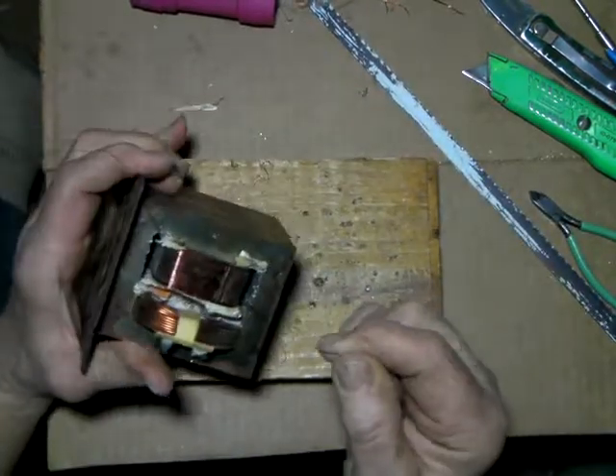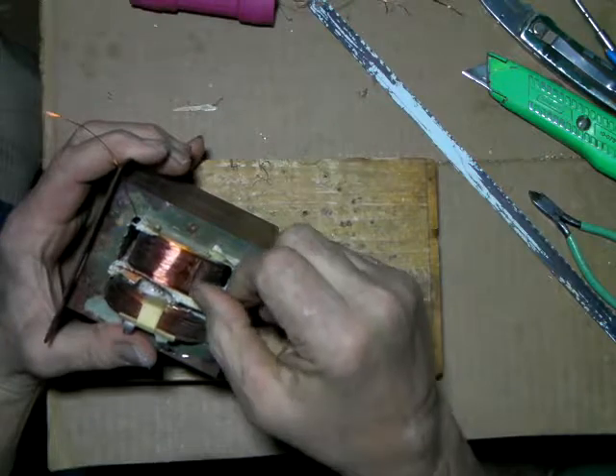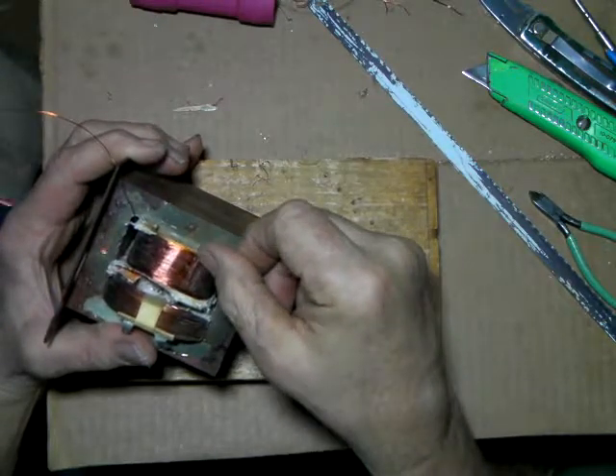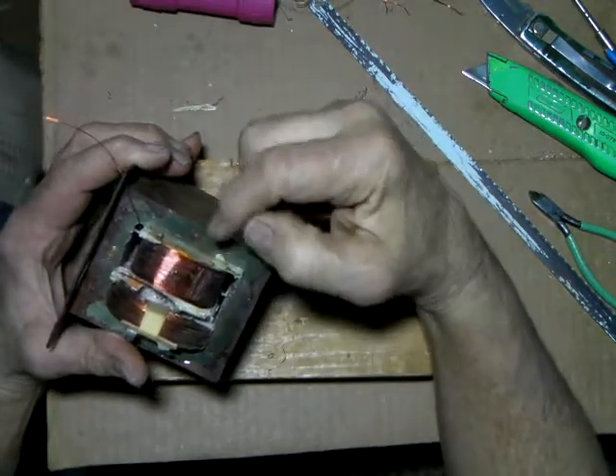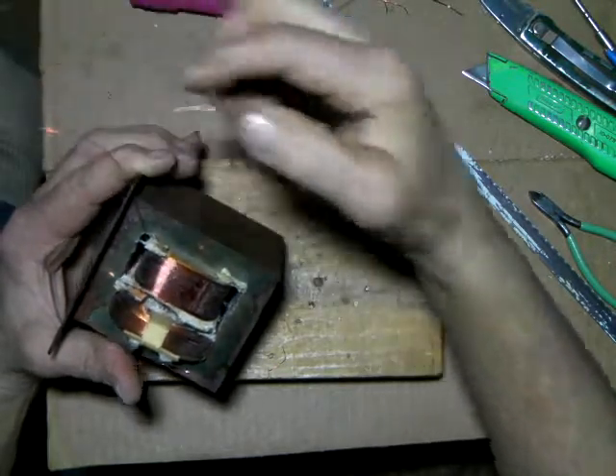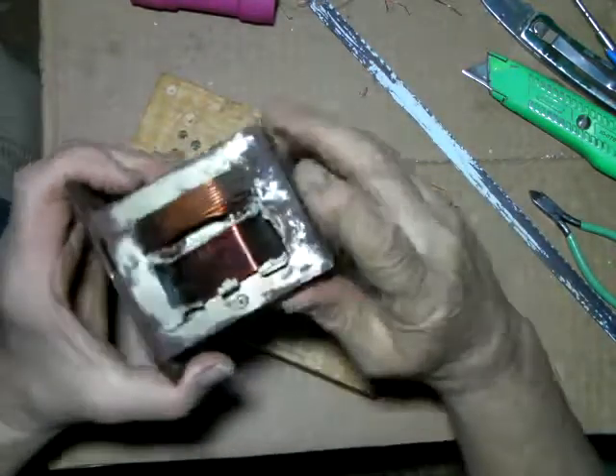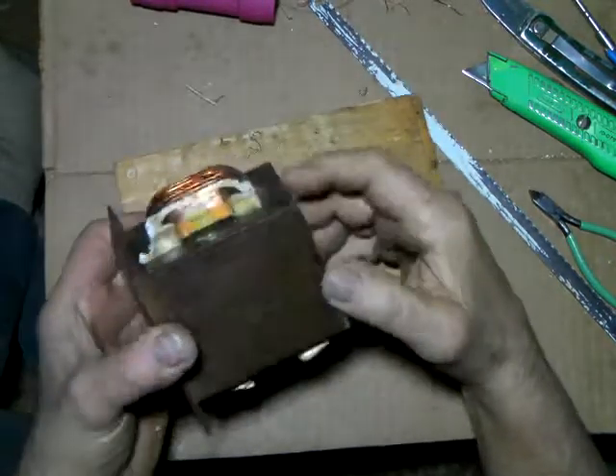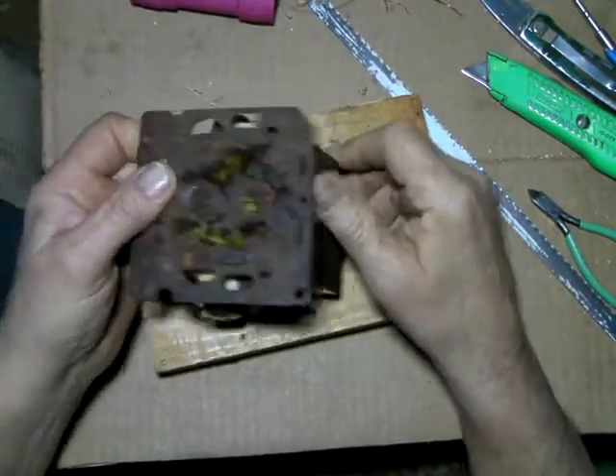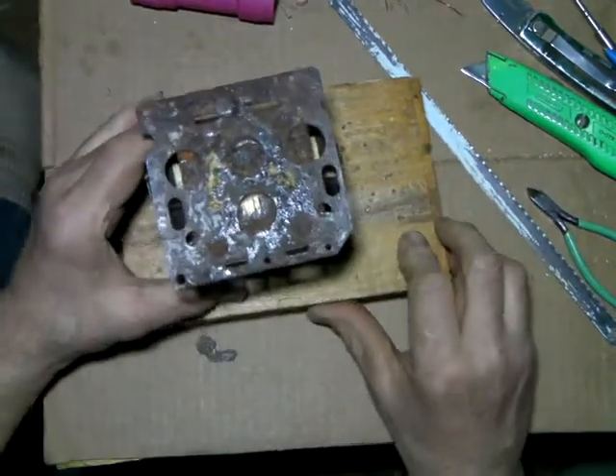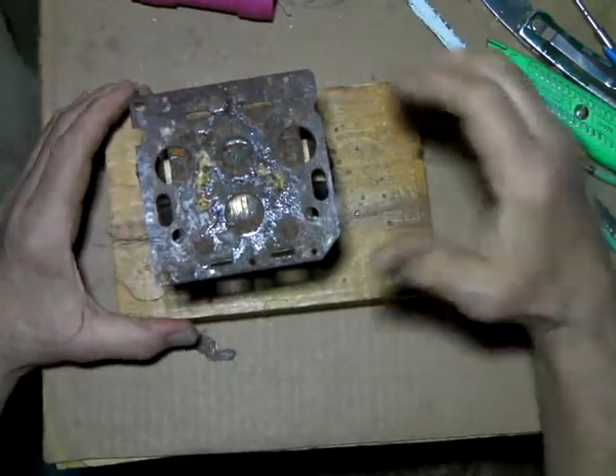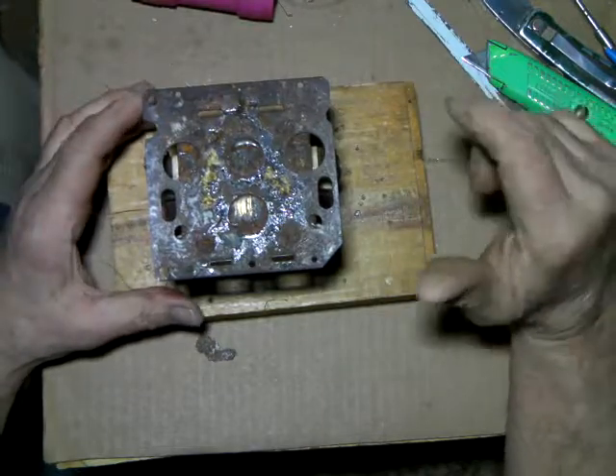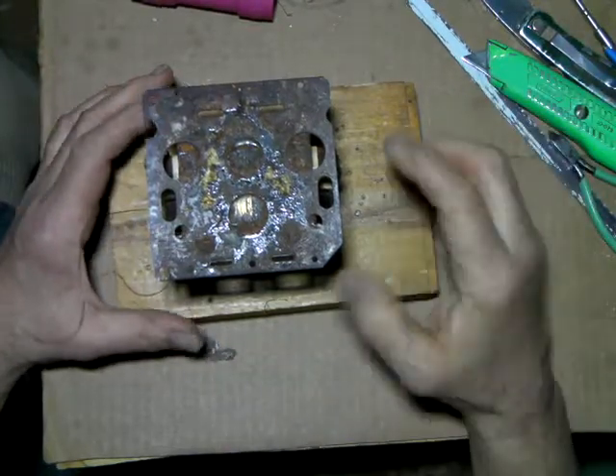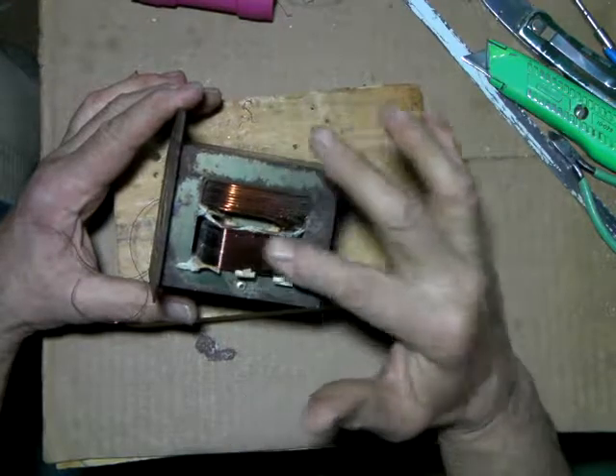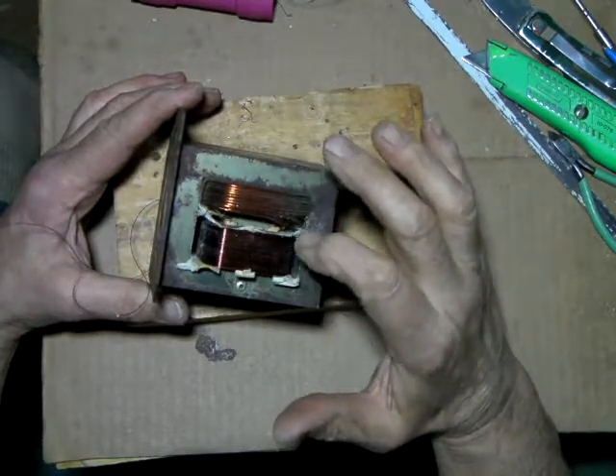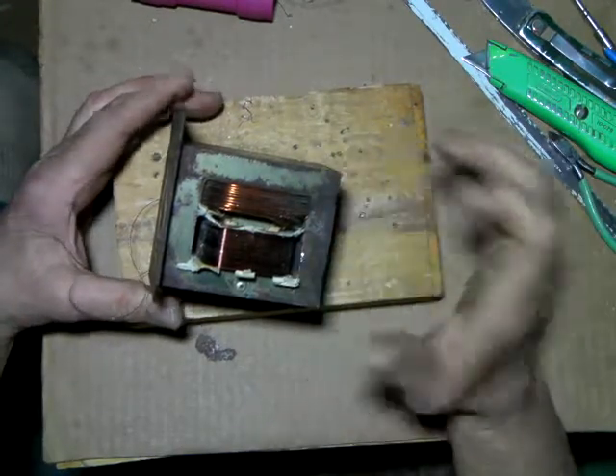You'll do this until you've finally peeled all that bad layer away, and when you get down to where you can get continuity between the wire and your ground contact, you've got it. Then hook it up to your full wave bridge and test your voltage at that point, to see if you've taken off enough turns to get around 2000 to 2200 volts.